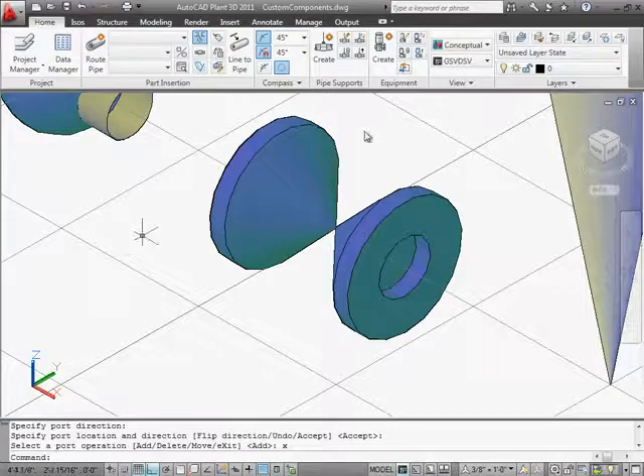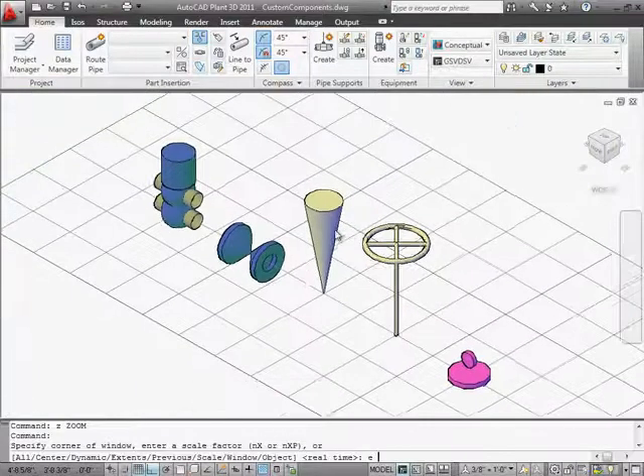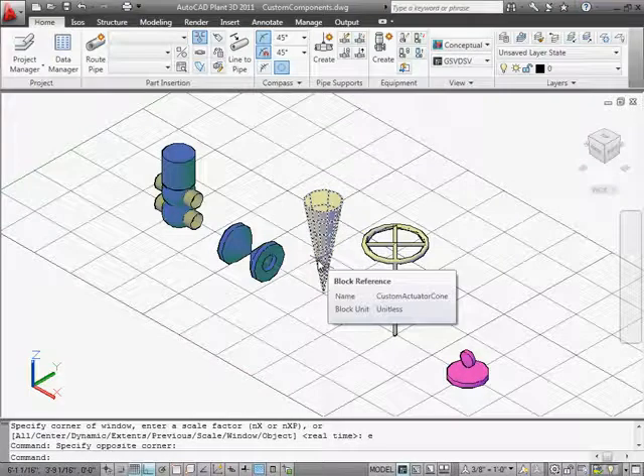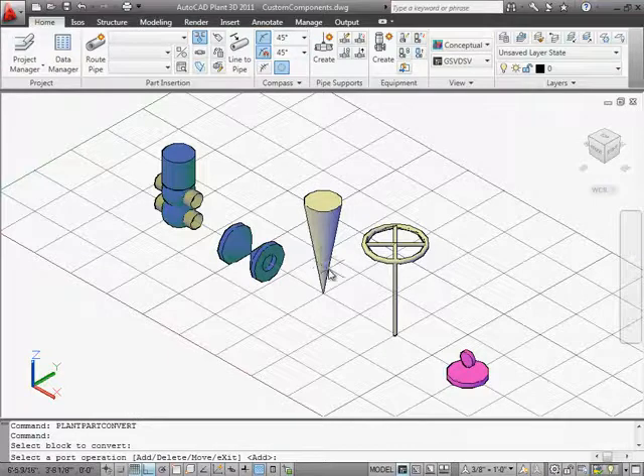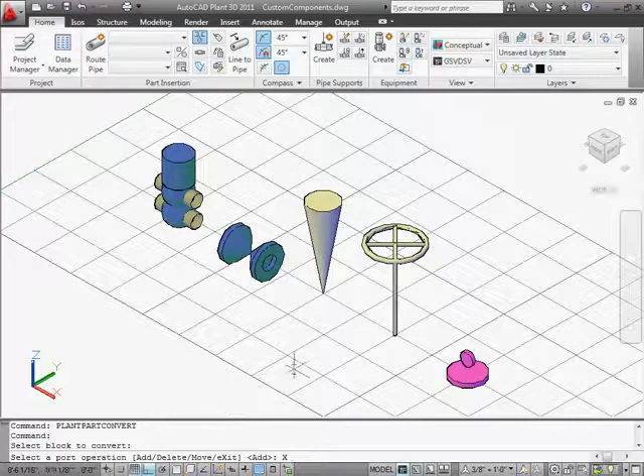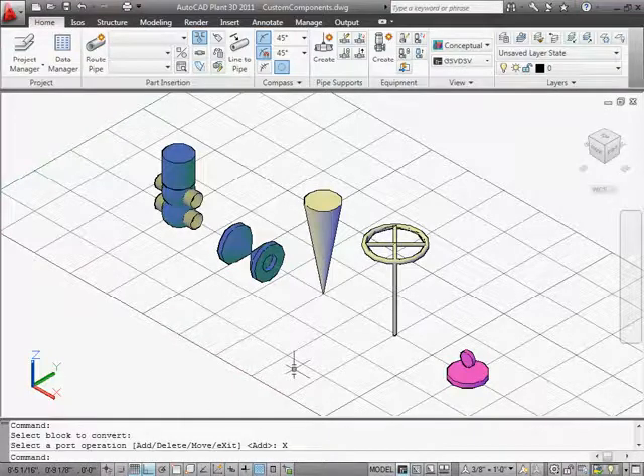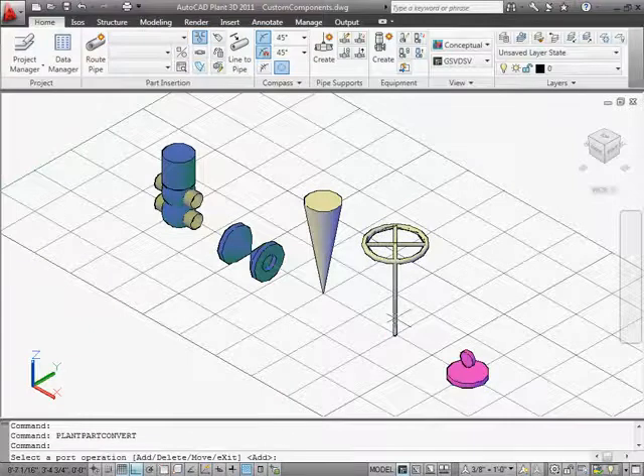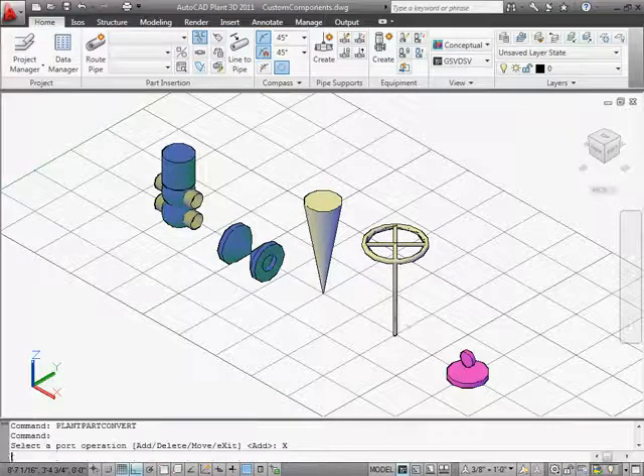Next we'll work on the actuators. Actuators are different because they don't have ports, but we still need to run the plant part convert command so that the catalog editor can recognize them and add them to the catalog. So you run the plant part convert command, click on the actuator, and exit. Do not add a port to these — actuators must have zero ports. We'll run this plant part convert command on both actuators, just clicking on each and then exiting.